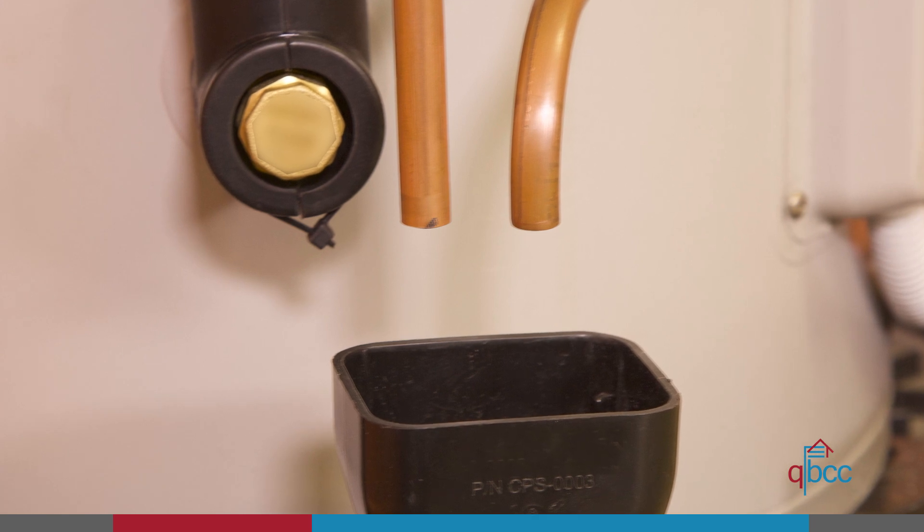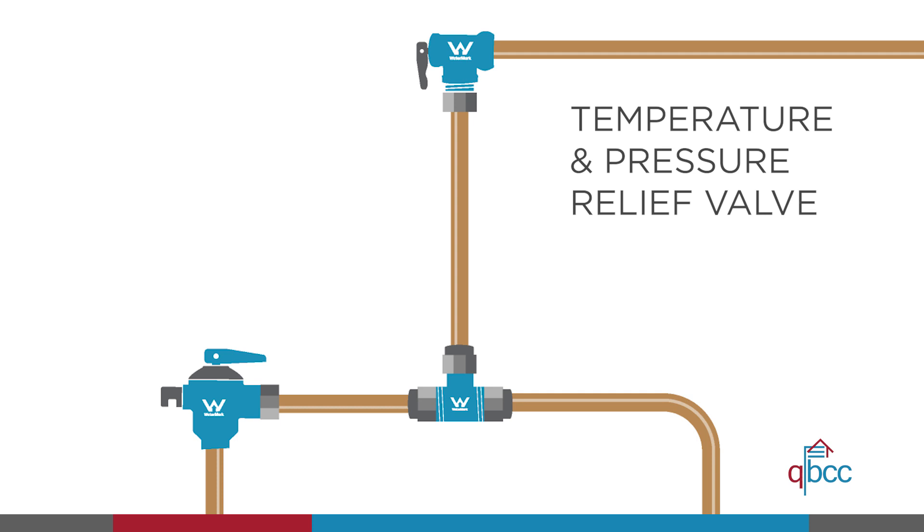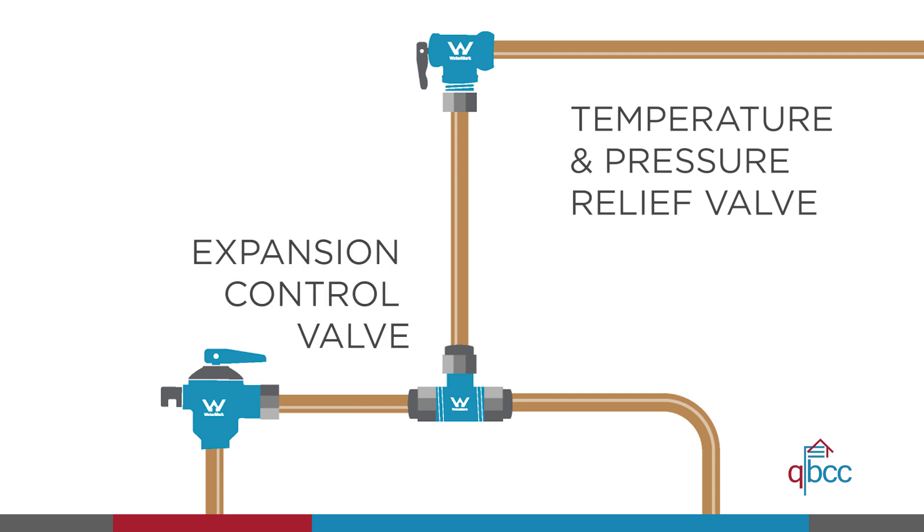When discharging over a tundish, drain lines must have an air gap that is at least twice the diameter of the drain line. You may join the drain lines from the outlet of the temperature or pressure relief valve and the expansion control valve on an individual heater.